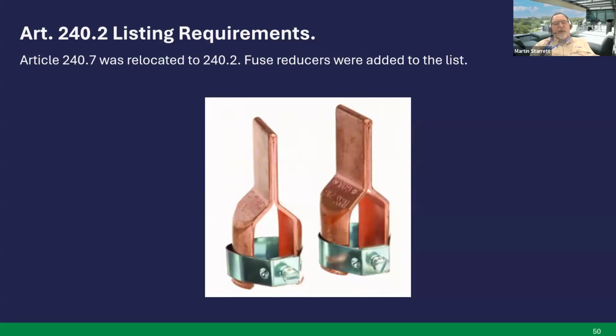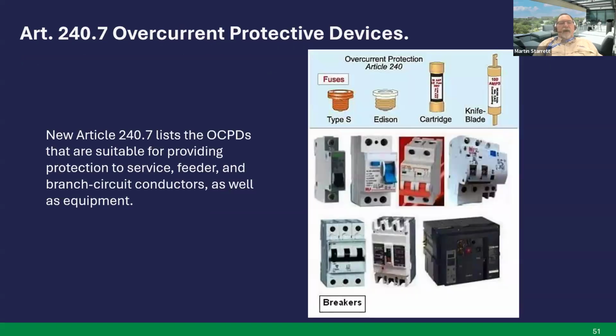Article 240.7 was relocated to 240.2 for the listing requirements. As I've been stating, almost all the listing requirements are now contained in .2 in each article. Fuse reducers were added to the list, so fuse reducers will have to be listed. Article 240.7, overcurrent protection devices. The new article lists the overcurrent protection devices that are suitable for providing protection to service, feeder, and branch circuit conductors, as well as equipment. So now we've got a whole list of these. They're listed out in Article 240.7.